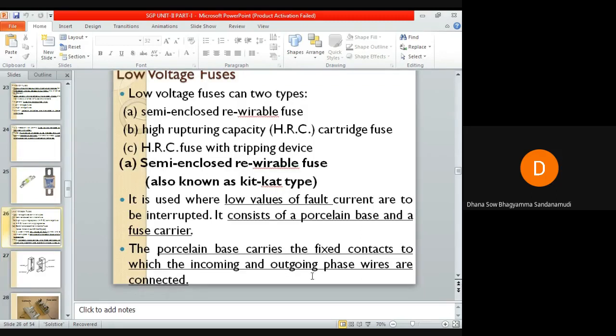So low voltage fuses can be further categorized into semi-enclosed rewirable fuse, high rupturing capacity cartridge fuse, high rupturing capacity fuse with tripping device. So the low voltage fuses can be categorized into three types, that is semi-enclosed rewirable fuse, HRC cartridge fuse, HRC fuse with tripping device. So let us discuss one by one in detail. The first one is semi-enclosed rewirable fuse. You can even call it a KitKat type fuse.